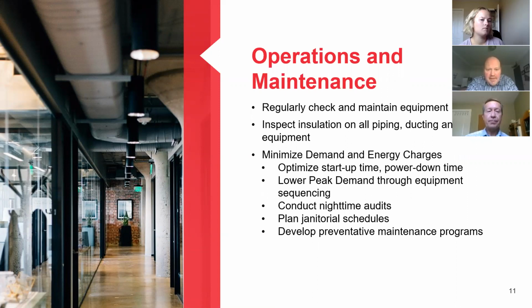Minimize your demand and your energy charges. Optimize your startup time and power down times. Starting up all your equipment at the exact same time, like Rogers mentioned before, will set a new peak demand. So if you can stagger that startup time, and not operate all the equipment at the exact same time, you're going to reduce that overall demand. Same thing with sequencing: lighting, fans, all these things can be started up at different times and can be sequenced through building automation systems.